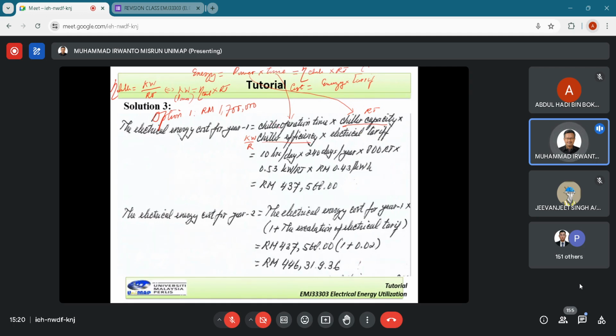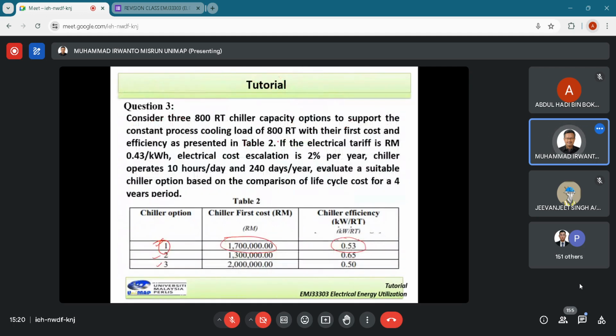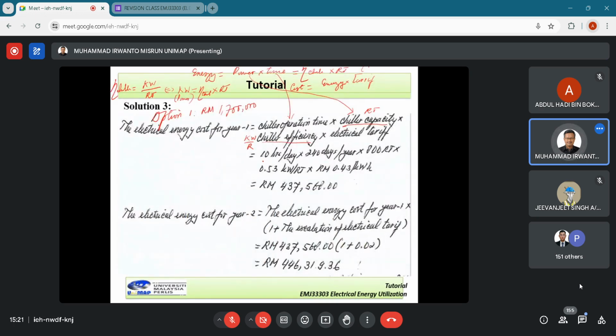Okay, so chiller operation time is given by 10 hours per day and 240 days per year, because we want to find the cost per year. So 10 hours per day multiplied by 240 days per year, and then chiller capacity 800 RT.